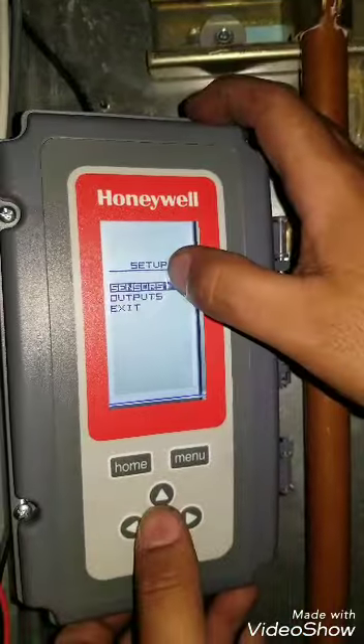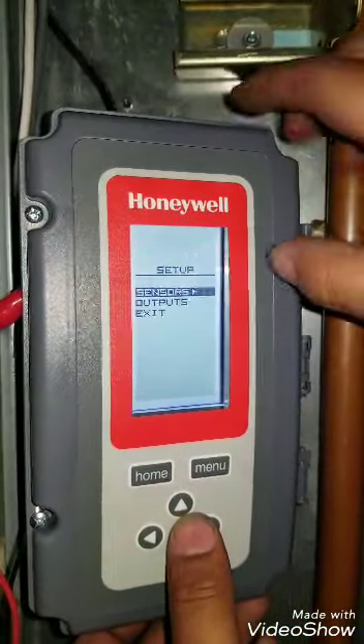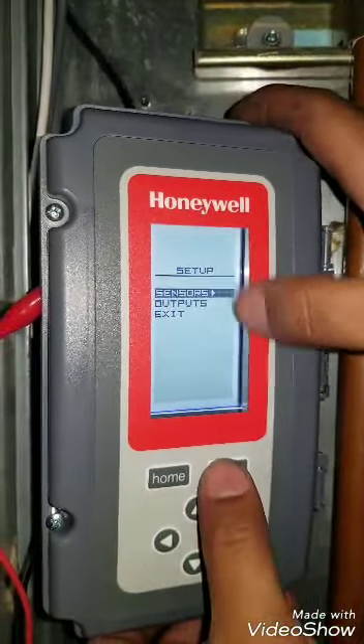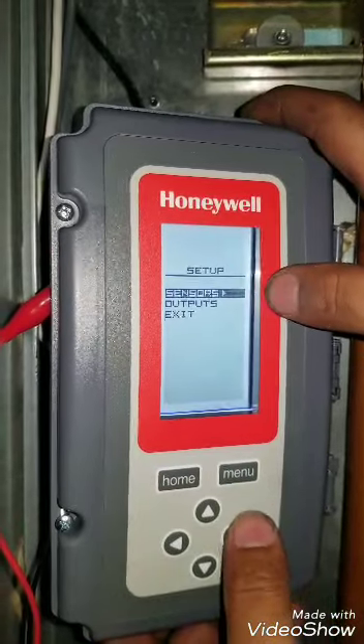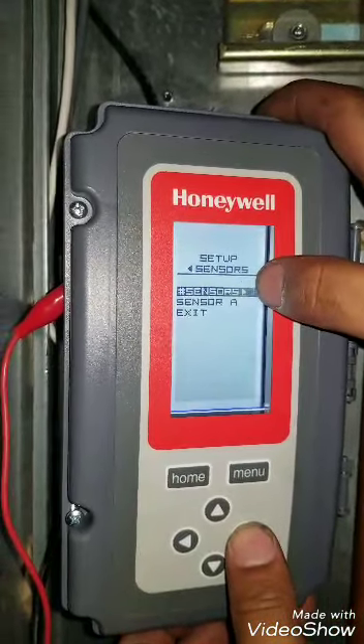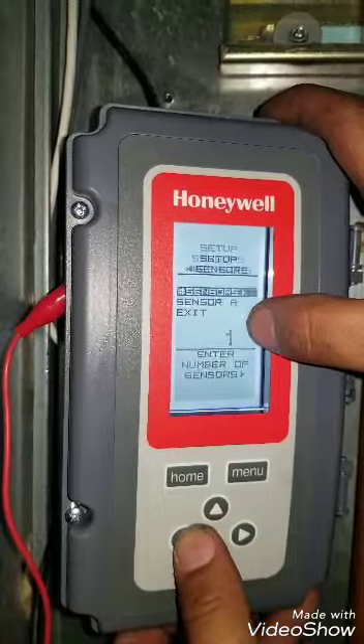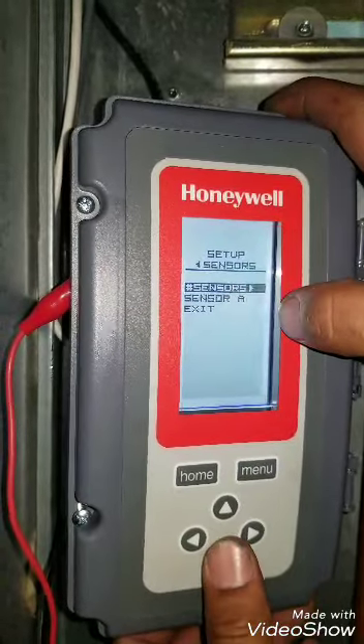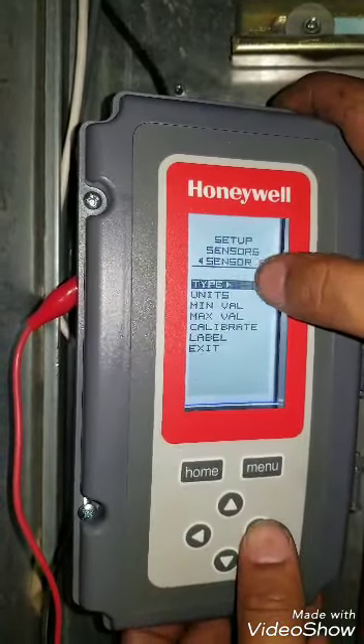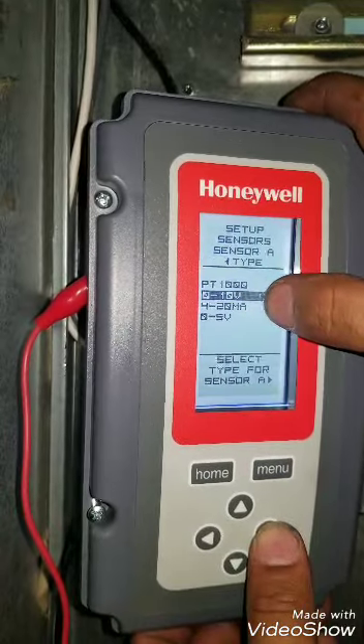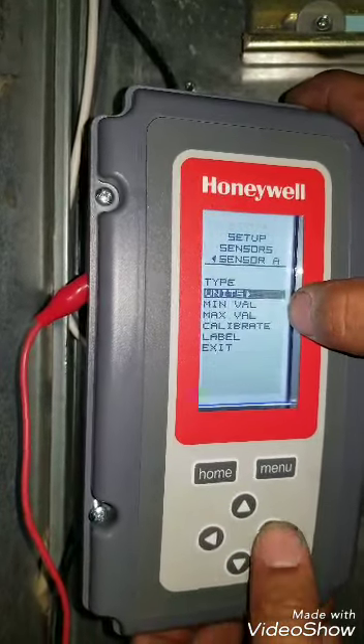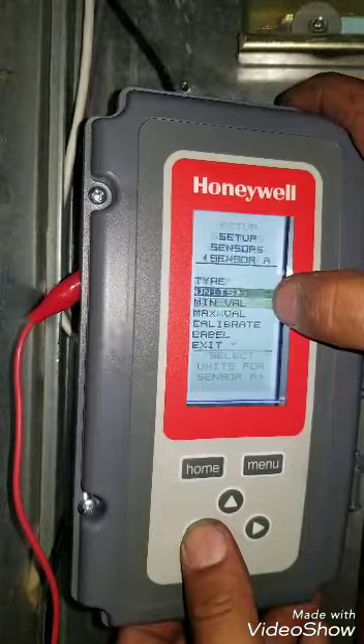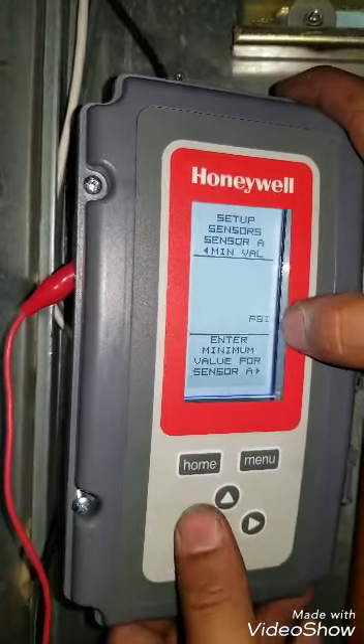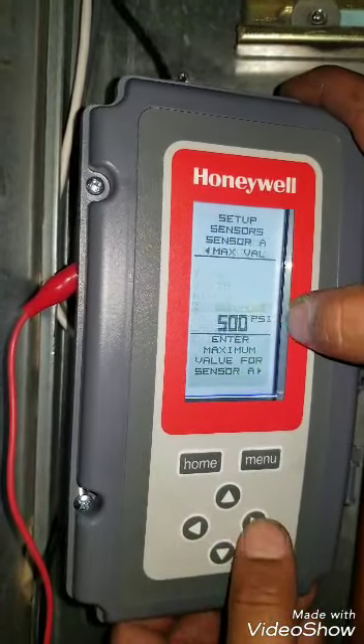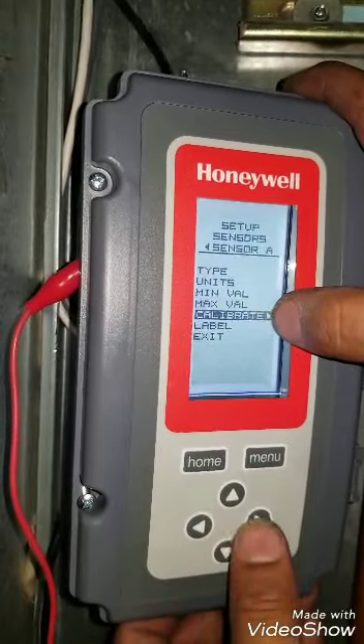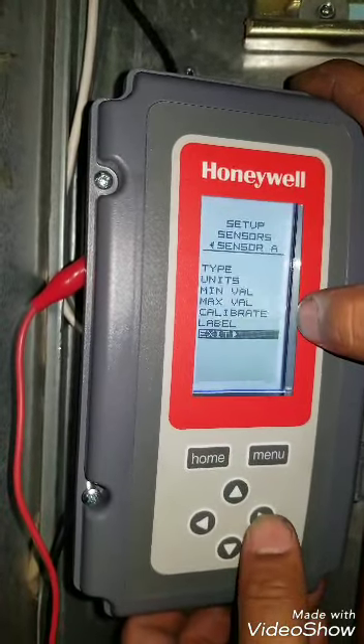Okay, so basically to cover everything, you hold menu until you get to setup. You go to sensors, number of sensors, 1. You go back, you go down to sensor A, type 0 to 10 VDC. Back, you go units, you want PSI. Back, 0 PSI, max 500 PSI. Calibrate, you can leave it. Label, you can leave it. You can go to exit.